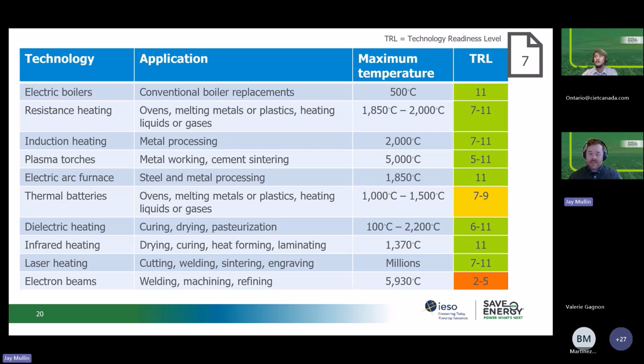Thermal batteries are starting to become available and demonstrated, and they can help manage electricity time-of-use costs and demand costs that drive increased operating costs. The downsides are capital costs and space requirements. We also have dielectric heating, which can be good for some systems like cooking or drying where water evaporates and can escape the system, but it's not as broadly applicable as something like heat pumps.